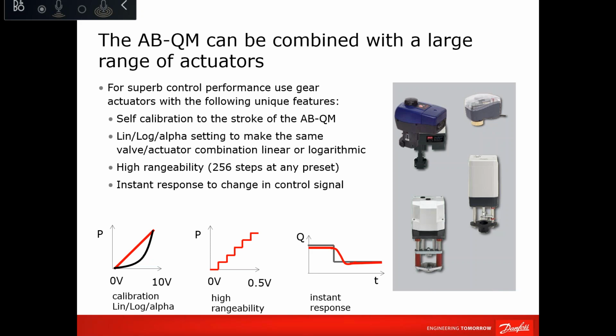And this is achievable because most old actuators have a limit switch at the close position in order to protect the motor from overload. So what we did, we didn't make it hardware, we made it processor based, and we put two limit switches, or end travel limit switches, one for full open and one for full close. By doing so, if you set the same valve, the same size, at two different settings and put two actuators on them, one actuator will modulate that preset percentage and the other actuator will modulate a different percentage. So regardless of the setting you put on the valve, the actuator will only modulate the setting you have done.